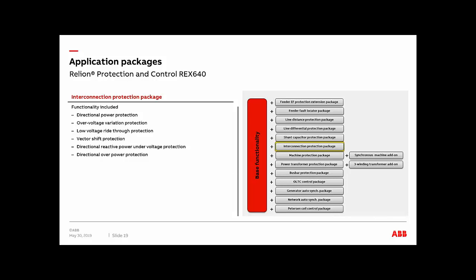We do also offer a vector shift protection. Pretty much this one just continuously measures the duration of a voltage cycle at the instance of islanding. What would happen is that the duration of the measured voltage cycle becomes shorter or longer, and that could be detected by the relay. That way it could give you an instantaneous trip when the shift voltage exceeds the set value that you put in your setting. So it's pretty useful for microgrid applications. And of course, you also have directional overpower protection. We'll call it 32O, and that's also available in your interconnection package.